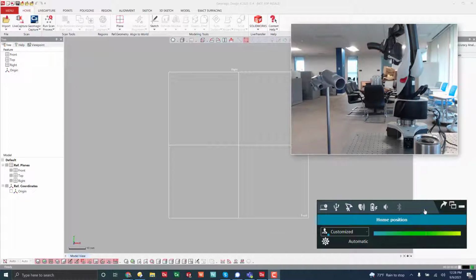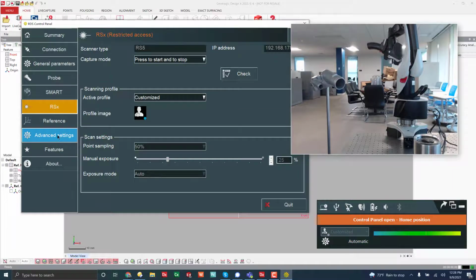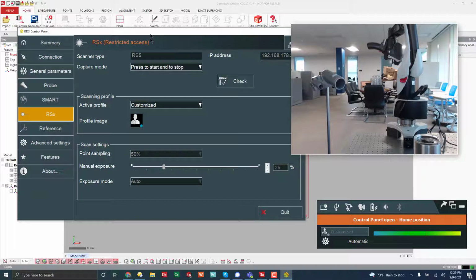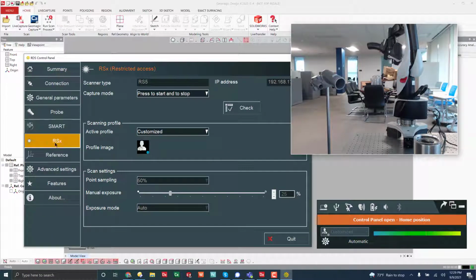Now, what I do before I actually go scan, I go into the hardware settings and just check their hardware settings. There's a few in here that I will utilize. Actually, because I opened this up before, it's automatically on the page that I usually change. So the RSX is the scanner section. I come in here and change my point sampling and even change my active profile. You also have the option here to change the press to start and stop on the trigger button over here on the arm. If you just tap it, it will scan, tap it, it will stop. You can actually change that to press and hold, which some people like to do.